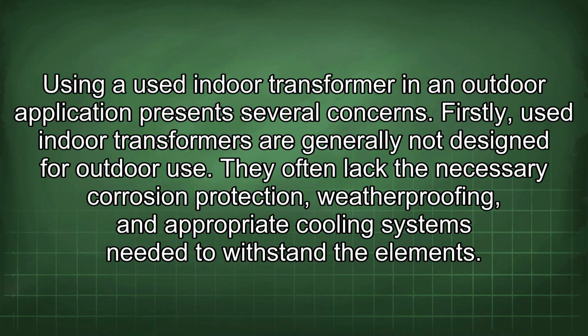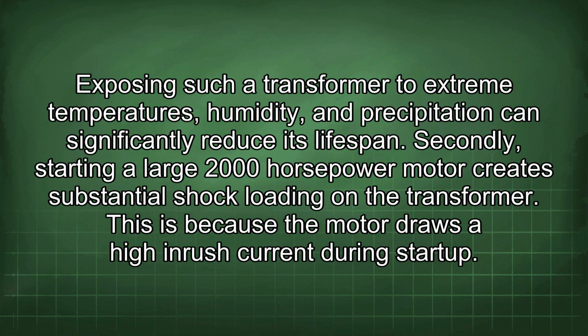Using a used indoor transformer in an outdoor application presents several concerns. Firstly, used indoor transformers are generally not designed for outdoor use. They often lack the necessary corrosion protection, weatherproofing, and appropriate cooling systems needed to withstand the elements. Exposing such a transformer to extreme temperatures, humidity, and precipitation can significantly reduce its lifespan.